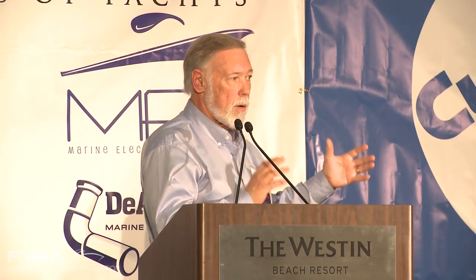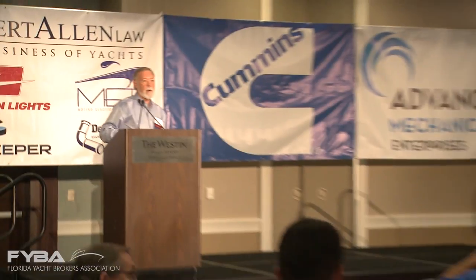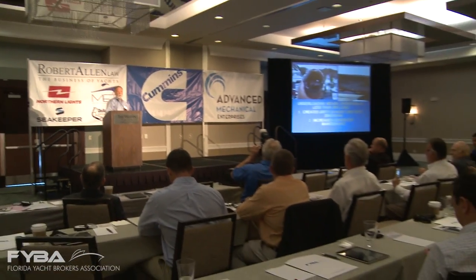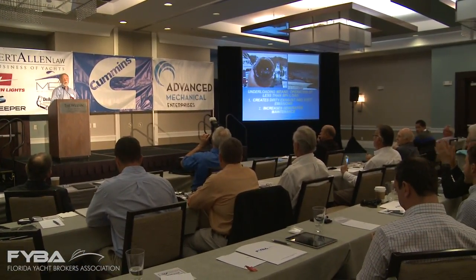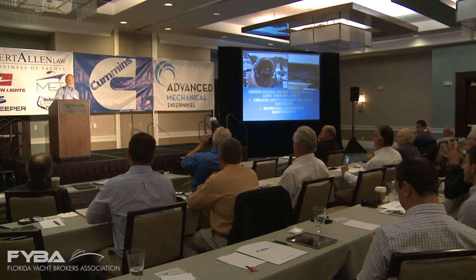And if it's a smaller boat that can't accommodate quite that much hardware, then it's a lot more important to really look at properly sizing the generator. So we'd really like to see the generator loaded to 50% load. I've repeated that about 10 times now. So, yes, sir. Would you define that specifically as in regular language, 5 kW, what's 50% load? Half load, 2.5 kW. Okay.